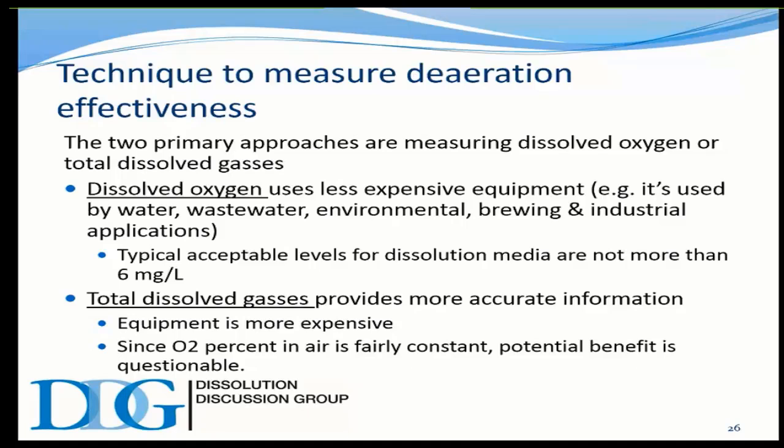But to me, this is right on the precipice. If it's a little over that, you might start to have interference from bubbles, but they're very difficult to see. Some bubbles are huge when media started off. It looks like you poured a carbonated beverage into a glass, and you see all the bubbles on the inside of the glass. It may look large like that, but when it's just over, it may be very tiny bubbles, very difficult to see, but it still does have an influence on dissolution.